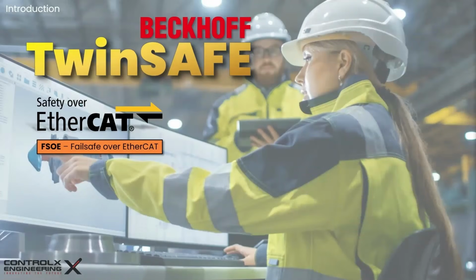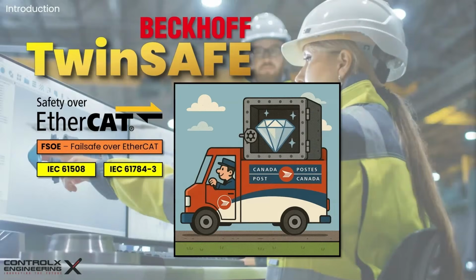With FSoE, the communication system is part of a black channel. In industrial safety, the black channel principle is a concept defined in IEC 61508 and IEC 61784-3. It allows transmission of safety-critical data over a non-safe communication medium, like standard Ethernet cables, without needing to certify every single switch, router, or cable in between. Think of it like sending a high-value diamond in a locked armored safe through a regular mail truck. You don't need to trust the mail truck or the driver, because the security is in the safe itself, not the truck.